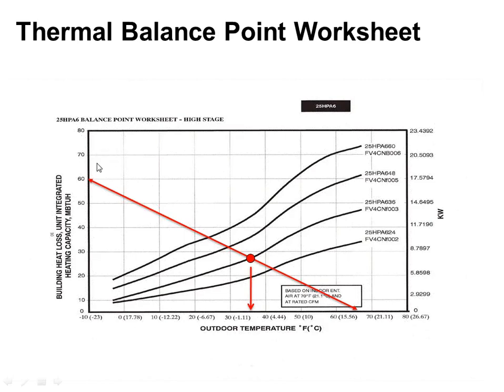The way we do them is we take one of these charts out of the book, and this is not even a variable speed unit on here. This is a regular two-stage unit. We take this chart from the book, which on the bottom goes from -10 to 80 degrees outside, and on the left goes from 0 to 80,000 BTUs. We plot this red line on the chart, which represents the load of somebody's house. And normally we do a load calc at the design point, which in this case, let's say is -10 degrees, and this guy needs 60,000 BTUs on a -10 degree day. Great, we plot that point.